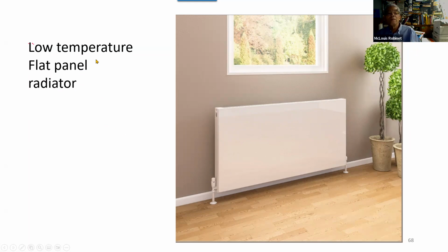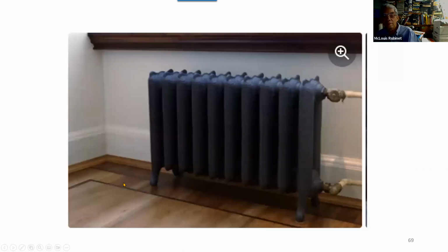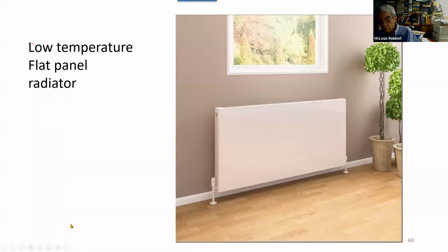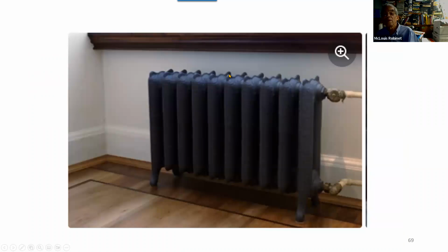But if you wanted to get a higher temperature, you could. But the question is, why would you want to do that? Heat pumps today, the maximum temperature, based on the choice of refrigerant and compressor, is in a range of 110, 120 degrees. So the traditional radiator doesn't have enough surface area for that to work.